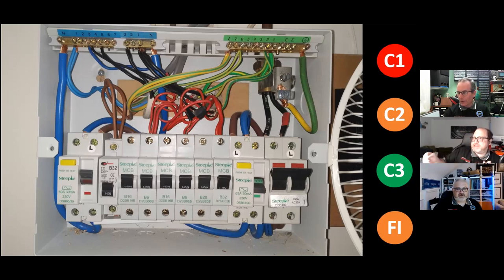When you have many of these little things like this, do you add each individual observation, or do you just do workmanship as one to represent those termination methods? See, all these little terminations are just slightly peeking out, all these little bits of copper. It depends on the inspector and the person ordering the work. Because for me, I would say swarf could be improved, C3.